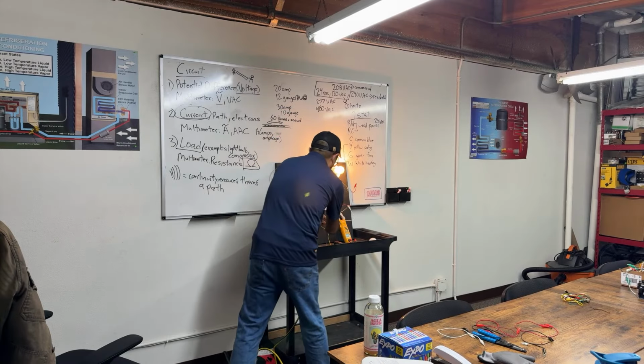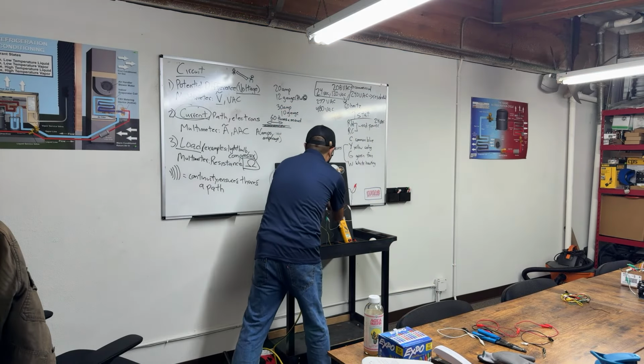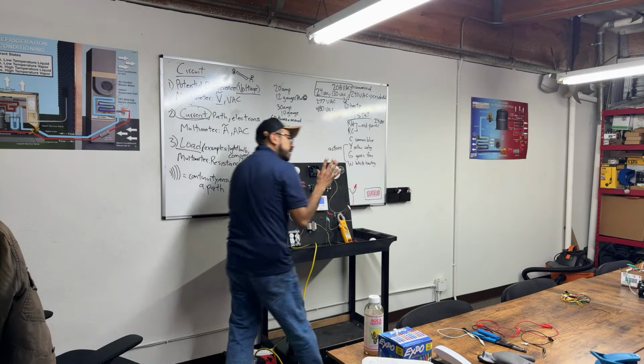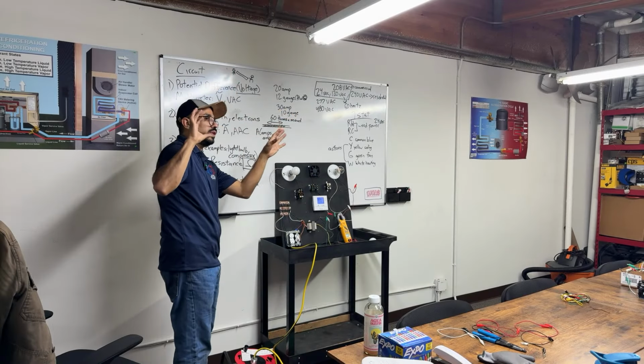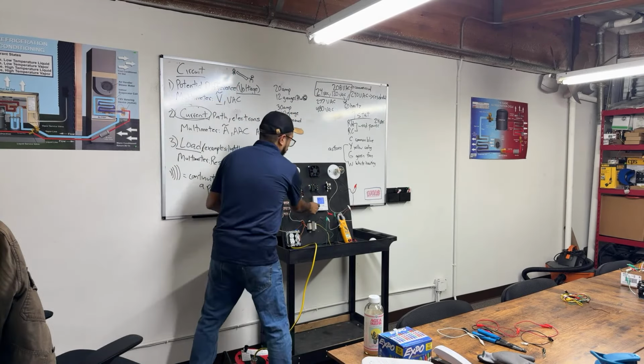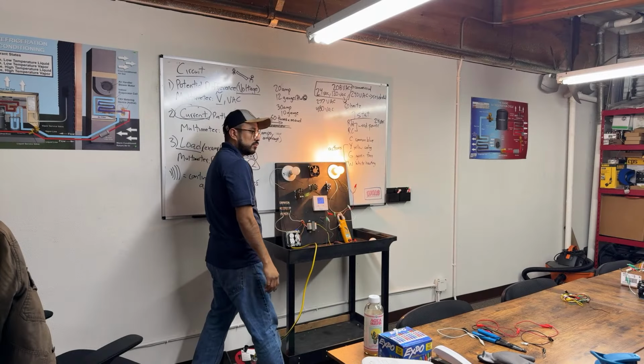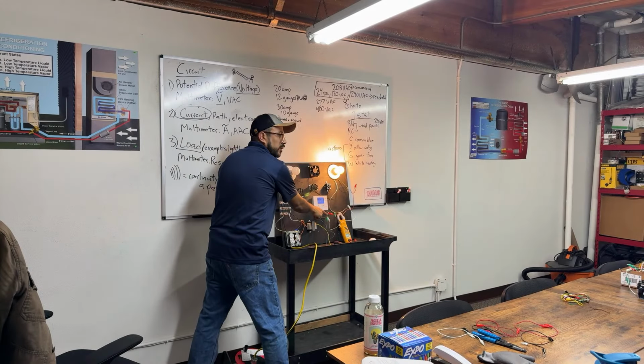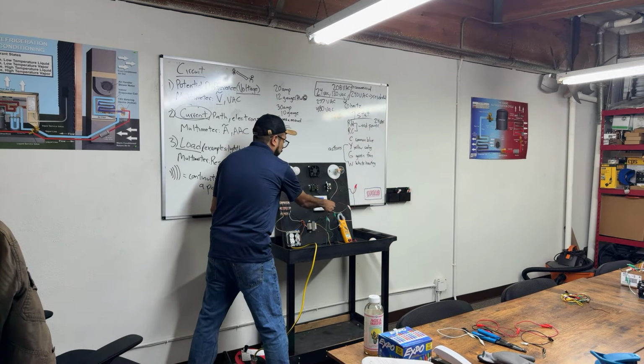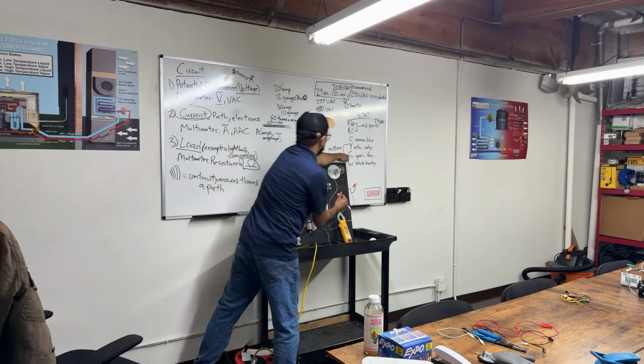For the fan, same thing. Turn the fan off. This is an independent fan, meaning it's not going to be hot or cold, just air coming out. On, there you go. Now it gave power on the G, the green wire. But if I have it somewhere else, nothing's going to happen, because we just said green is for the fan.